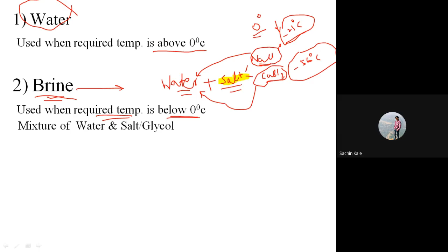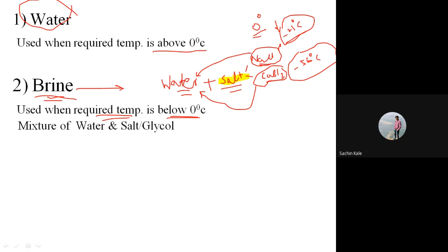Sometimes instead of salt you can use glycol also, inside the water. That glycol may be ethylene glycol, or that glycol may be propylene glycol. Whenever you are mixing glycol along with water, whatever brine solution will be formed will have the temperature below 0 degree centigrade, and because of that, you are able to use that brine solution for achieving the required temperature below 0 degree centigrade. So this is related to the secondary refrigerant.